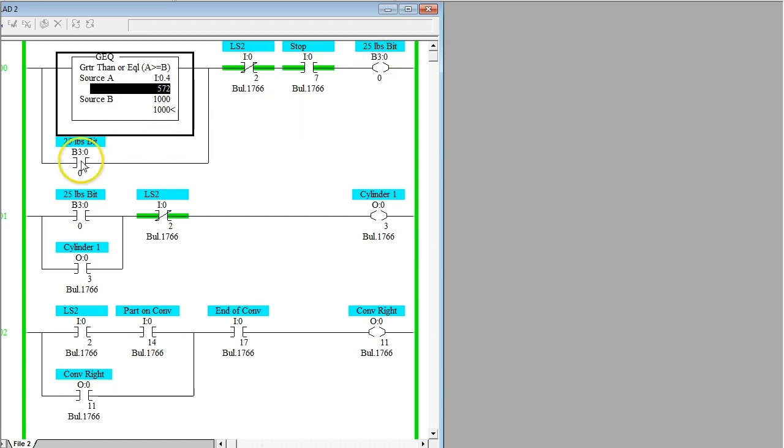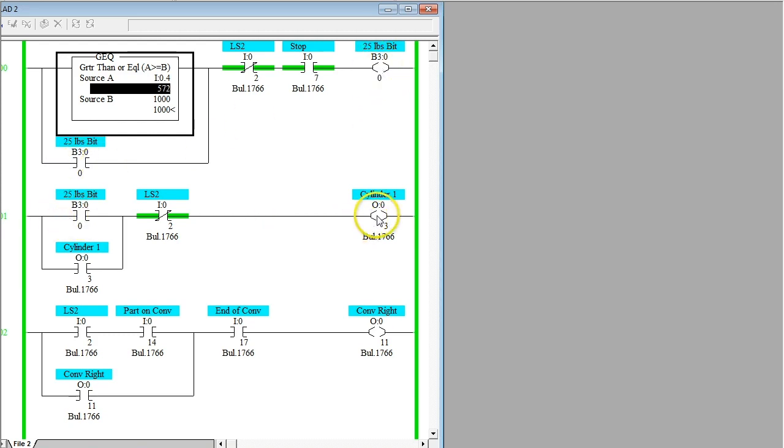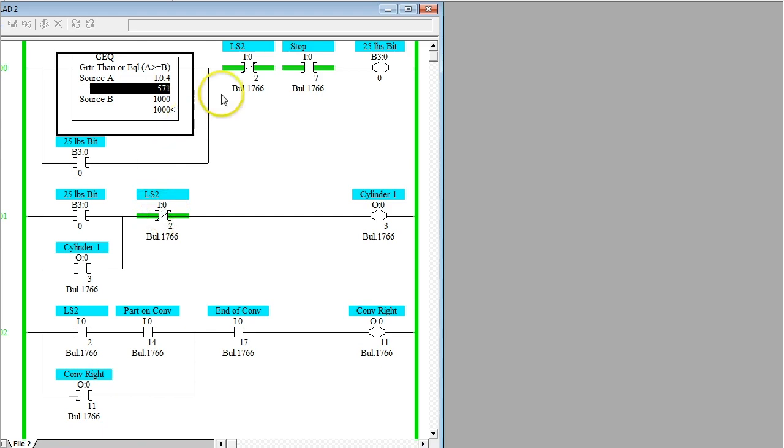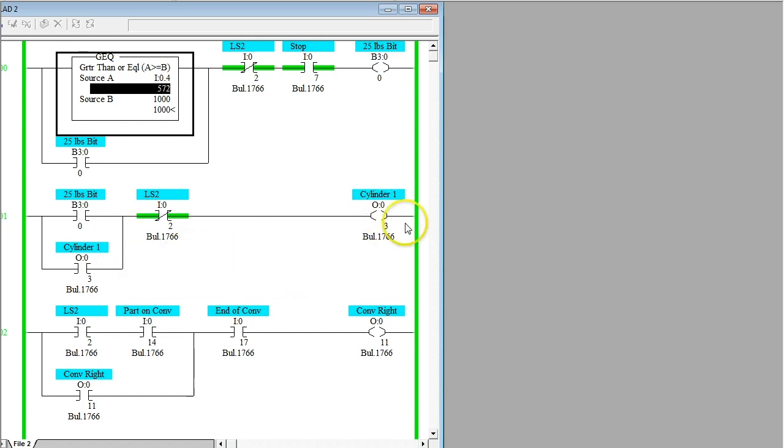Once that's activated, this will drop memory in. Also at the same time, my cylinder one, which is controlled by a 4-2 directional control valve solenoid activated spring return, will extend. When the cylinder is all the way extended, it will activate LS2, which will turn off this bit 3 here and deactivate the memory of the cylinder going out, allowing the cylinder to retract.